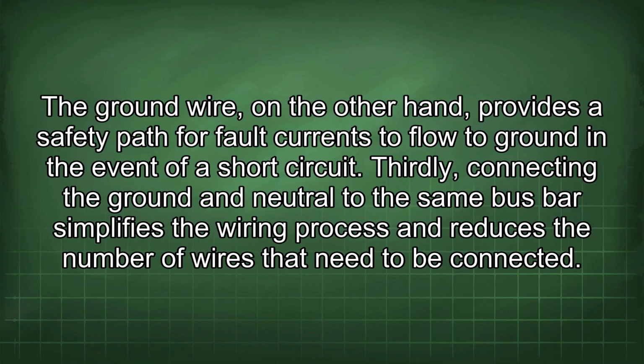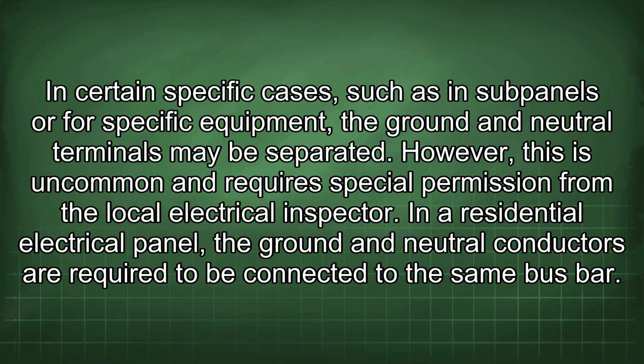Thirdly, connecting the ground and neutral to the same bus bar simplifies the wiring process and reduces the number of wires that need to be connected. In certain specific cases, such as in subpanels or for specific equipment, the ground and neutral terminals may be separated. However, this is uncommon and requires special permission from the local electrical inspector.